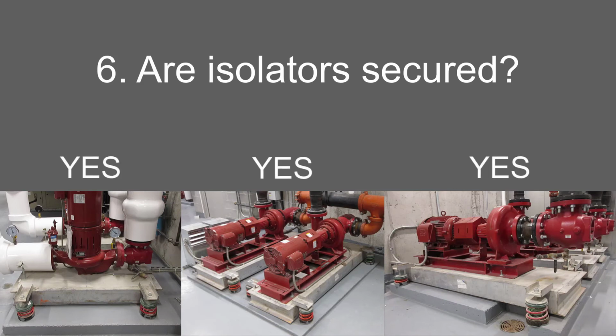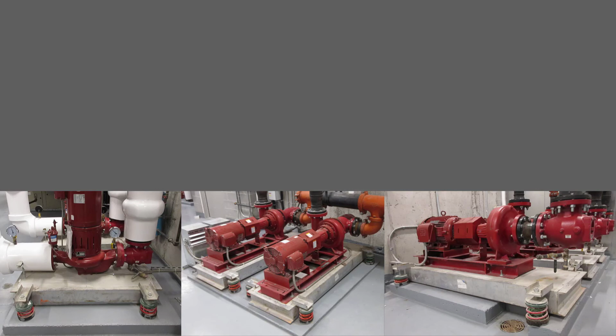None of the bottom cups were bolted to the floor, which was not a project requirement and not really necessary in this case since they will see negligible lateral loads. The isolators for the chilled water pump that were slightly overhanging the edge of the housekeeping pad, though not ideal or recommended, have enough support under them to not slip or tilt, so it can be considered close enough.